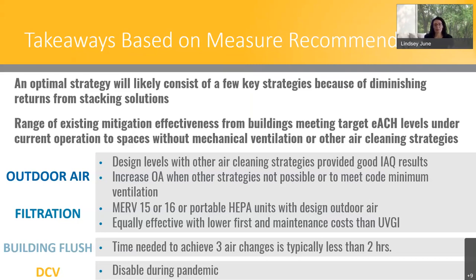As far as outdoor air levels, increasing outdoor air levels when feasible was the highest energy impact across the studies. And because of this, using design outdoor air levels in combination with either filtration or UVGI was a prominent strategy for energy savings. For filtration, typically MERV 15 or 16 rated filters or portable HEPA filters enable significantly reduced outdoor air levels while achieving equivalent airborne exposure reduction and energy savings, and can be equally effective as UVGI with lower first costs and maintenance costs.